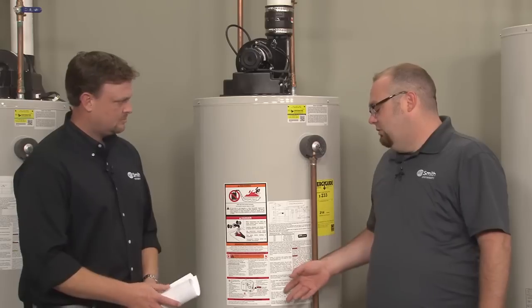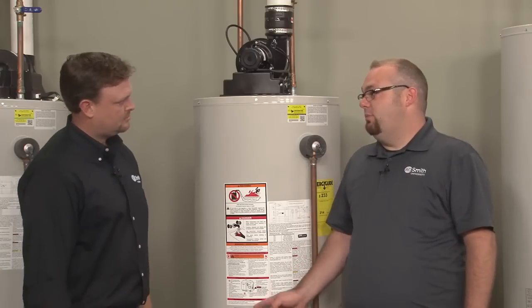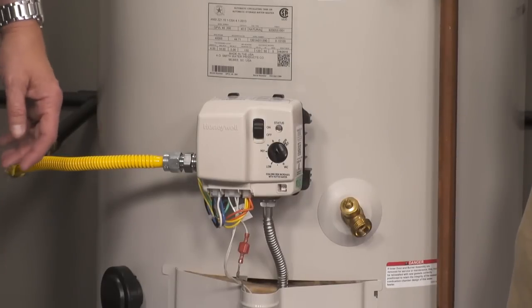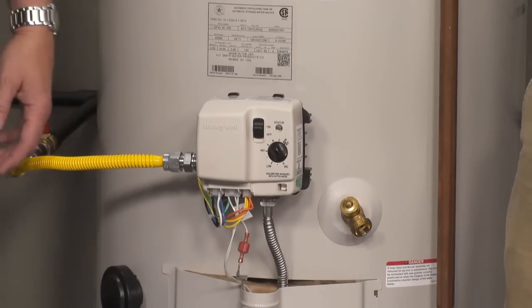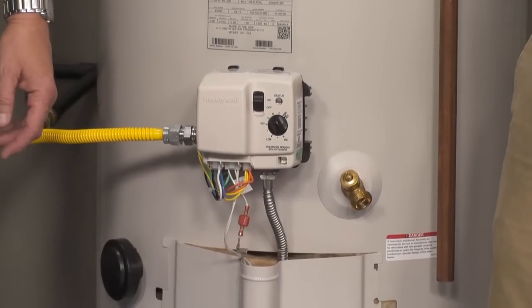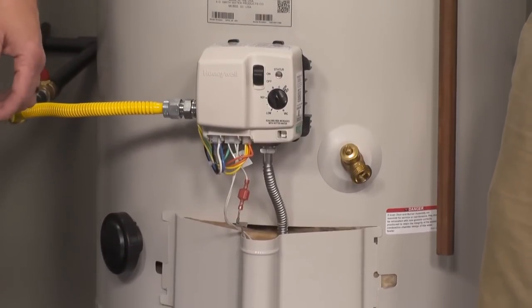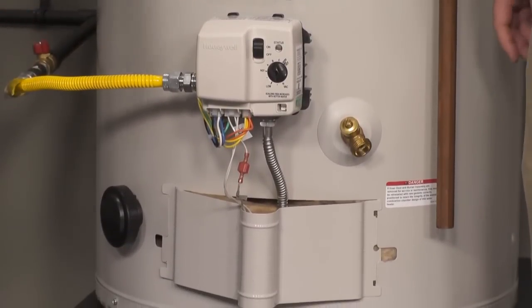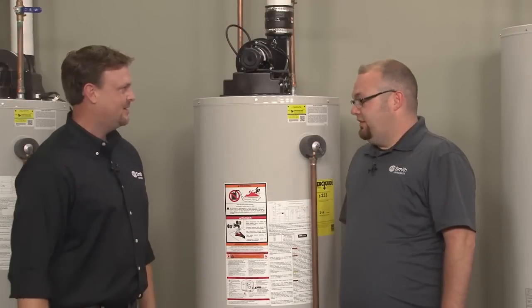But first thing I want to do is cycle power off, cycle power back on, and check to see. I have to look through the burner chamber. I'm going to see the igniter glow, but I'm looking for something special. I'm looking to see if the flame ignites after about 17 seconds. Okay, so it's either going to light or it's not, right? Yes, it's either going to light or it's not.